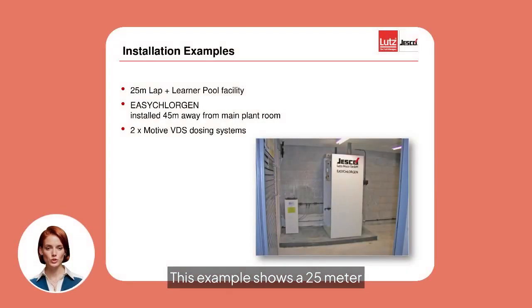This example shows a 25-meter lap and learner pool facility. Easychlorgen is installed 45 meters from the main plant room, demonstrating flexible siting. 2 motive VDS dosing systems distribute hypochlorite to the pools, ensuring consistent water quality while keeping chemicals safely contained.